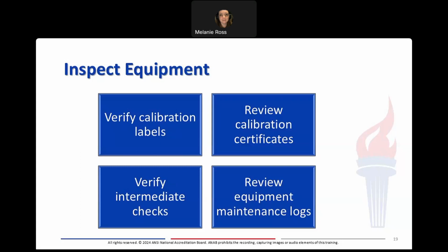The other thing that we can do is verify if there are intermediate checks that need to be performed, such as daily balance checks or maybe even continuing quality controls. So that box can mean a lot of different things. And then if it's important to your internal audit and to the audit criteria, you could look at those equipment maintenance logs as well.